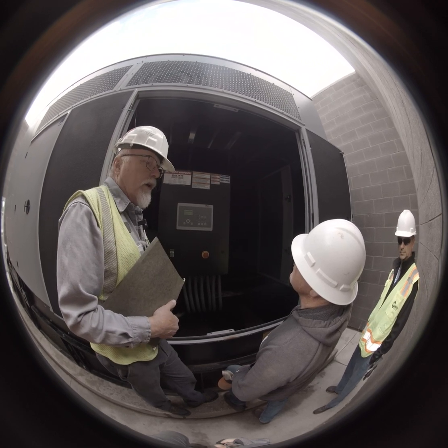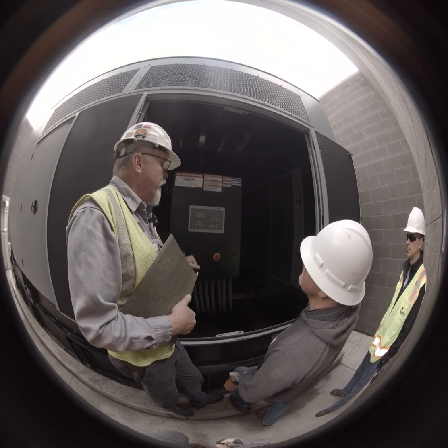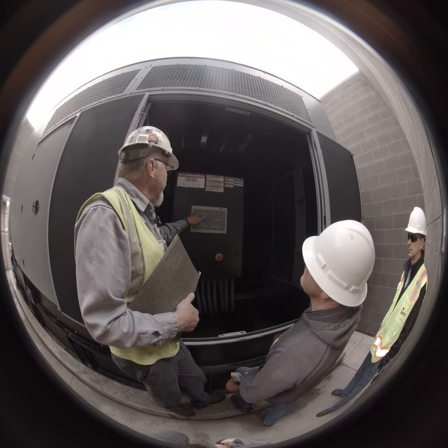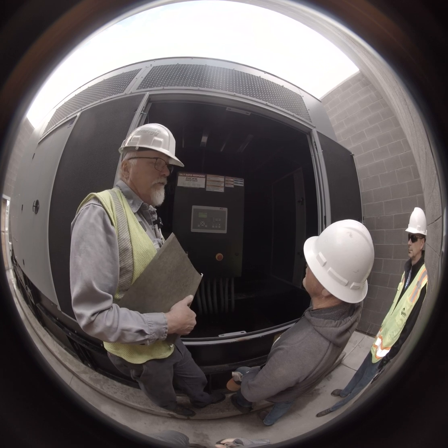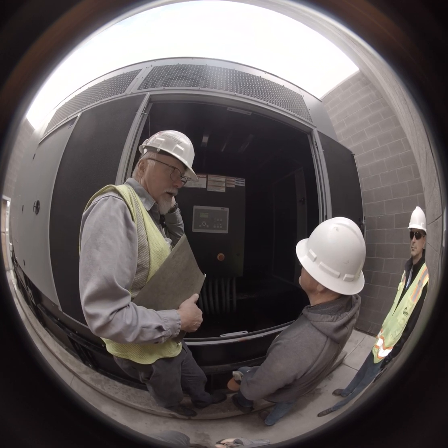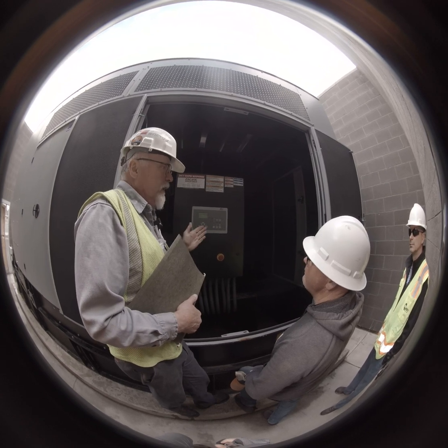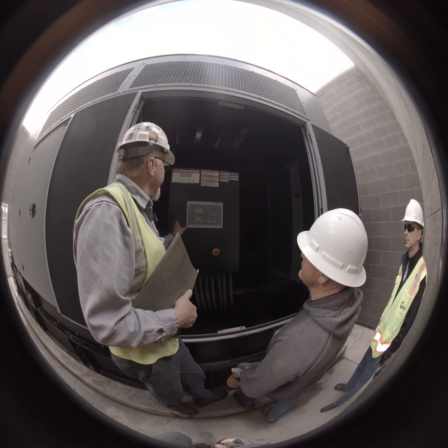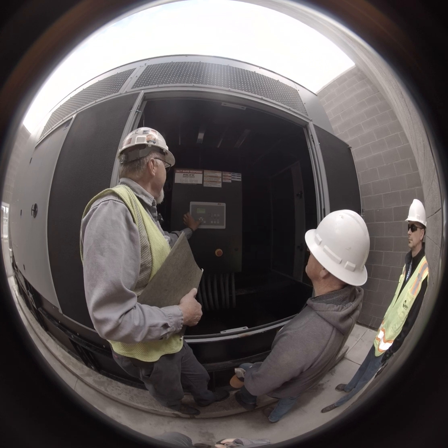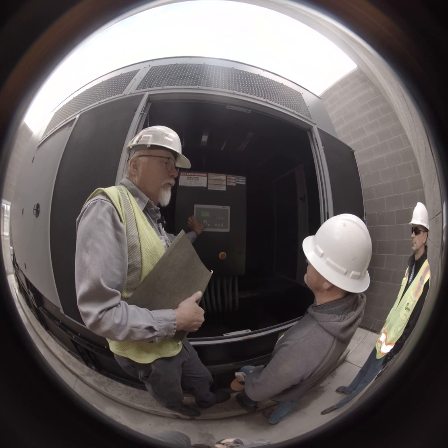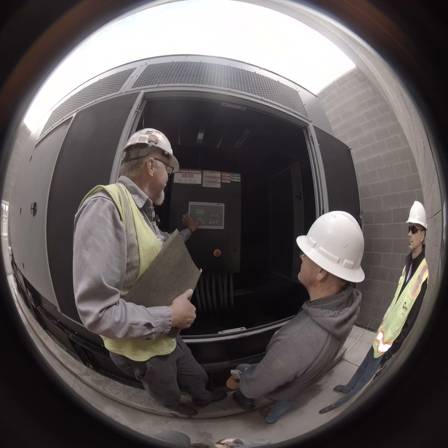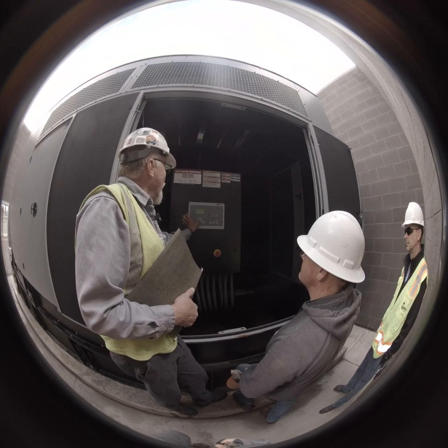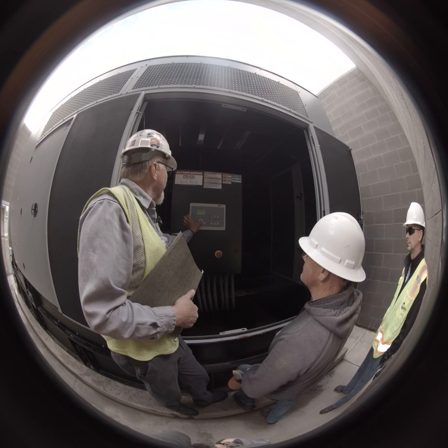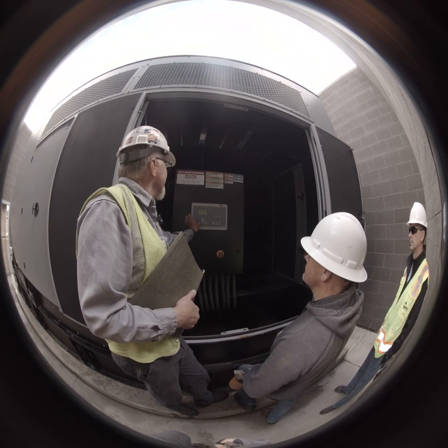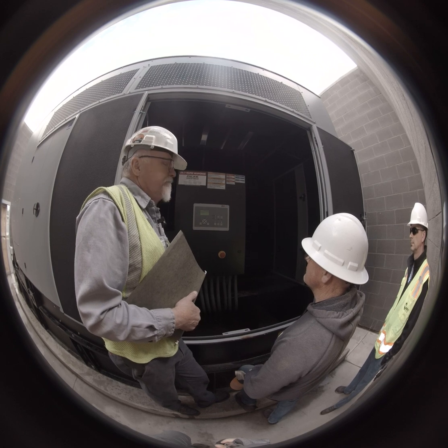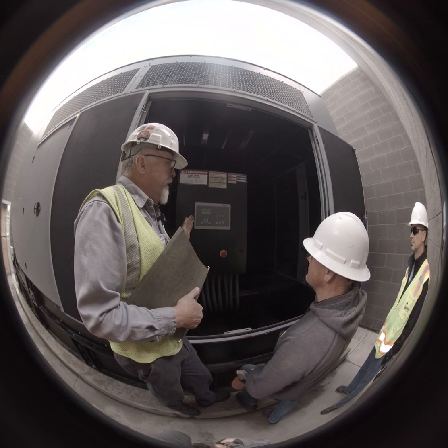Total kilowatt, if you want to go and look at your fuel chart, when this is running with your normal loads on it, come in and look at your total kilowatt, and you can figure out what percentage that is of the rating, and you can hit the chart and say, okay, I should be burning about this much fuel. kVA, kVAR, and all that stuff, I mean, if you really want to be techie about it, that's not really going to make a whole lot of difference in the real world. Okay, run stats. Run stats is broken down into 3 different levels.